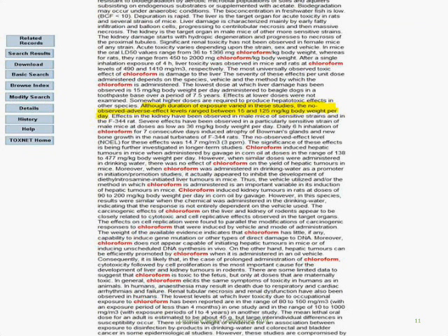What we're trying to determine is which of these levels is the best representative of our device. So which one has the most representative contact to the patient, the same route of administration and dwell time. That's the NOEL we want to use. In this real-life case, the NOEL of 15 was the most realistic.